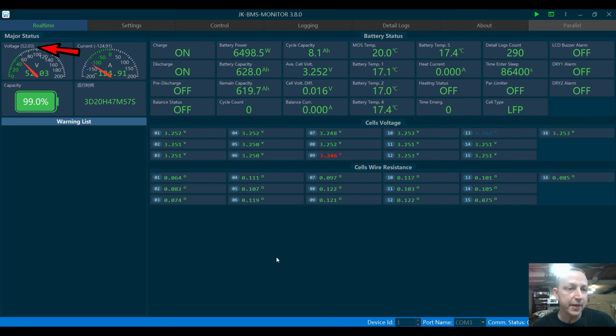All right, 52.03 volts, 125 amps, so almost exactly a 0.2 C, and that equates to 6,500 watts. All right, so I would say we're looking pretty good so far. Time now is 9:57 a.m. and this test should run for roughly 5 hours.